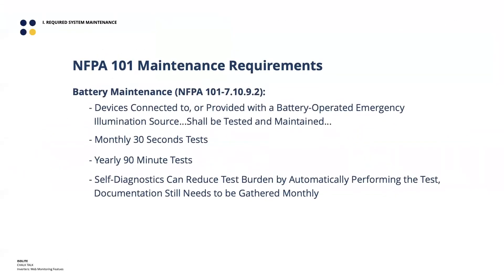When we talk about emergency lighting, exit signs, and inverters, we primarily care about NFPA 101, the Life Safety Code. There's a lot in Chapter 7 about the obligations and design of these systems, but in Chapter 7, Part 10, Paragraph 9, Section 2 is the information we're actually discussing today. It details the ongoing obligations the facilities team has to keep an emergency system code compliant. Any device connected to or provided with a battery-operated emergency illumination source shall be tested and maintained.